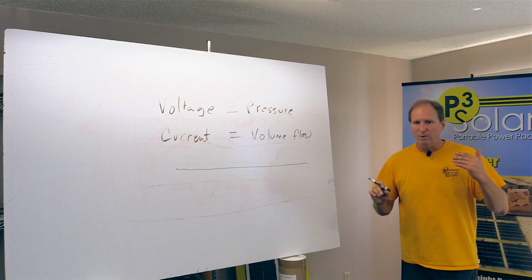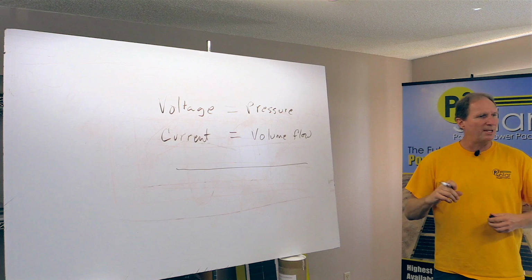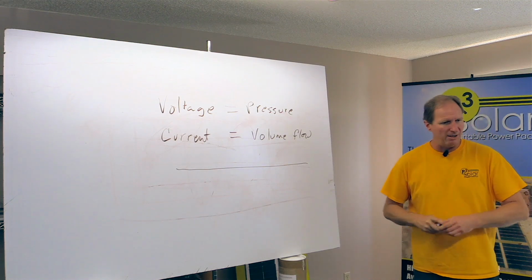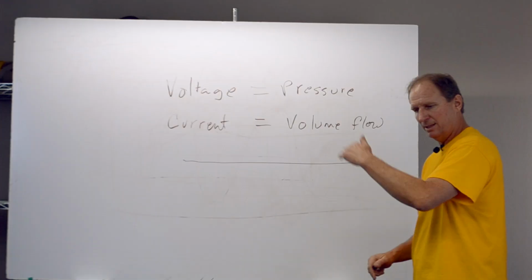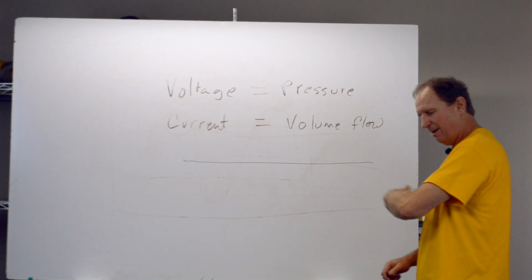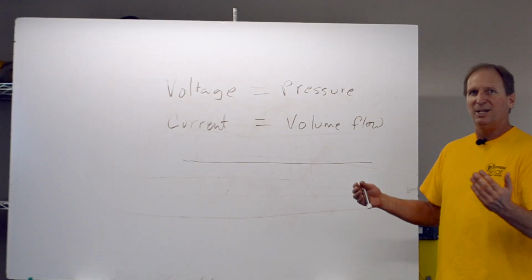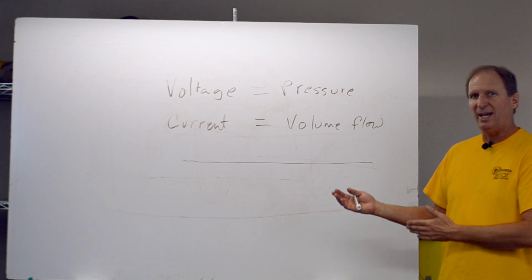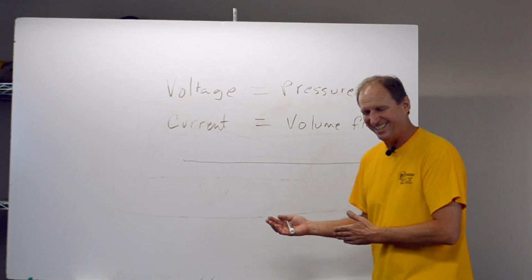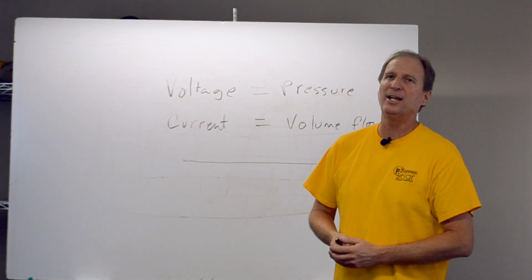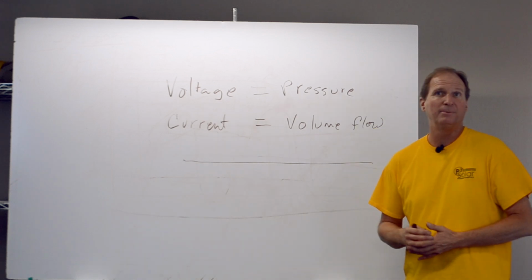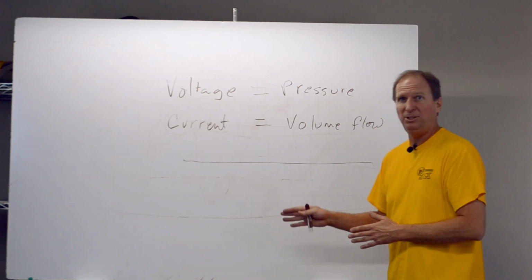So, you know, we see this a lot of times. Somebody will run wire from the back of the cart to the front of the cart, back to the back of the cart, back to the front of the cart, and they're using 14 gauge wire. Well, you're going to have a lot of voltage loss in that, and you're not going to move a lot of current because it's so long. So just keep that in mind when you do this.